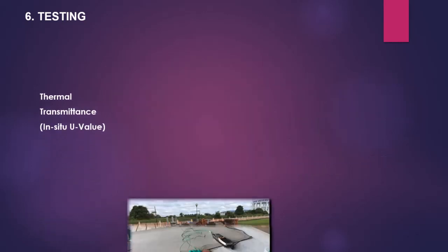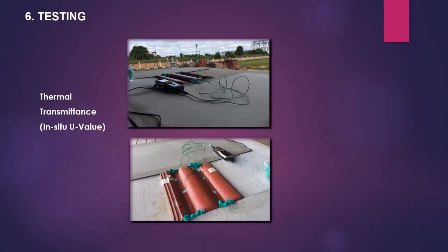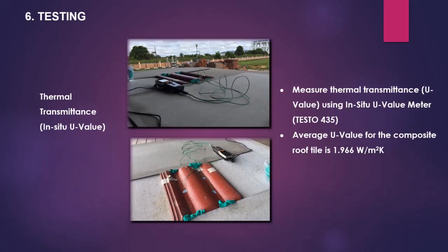The second test is thermal transmittance in-situ U-value measurement, conducted using an in-situ U-value meter, Testo 435. The average U-value for the composite roof tile is about 1.966 watts per meter squared kelvin.